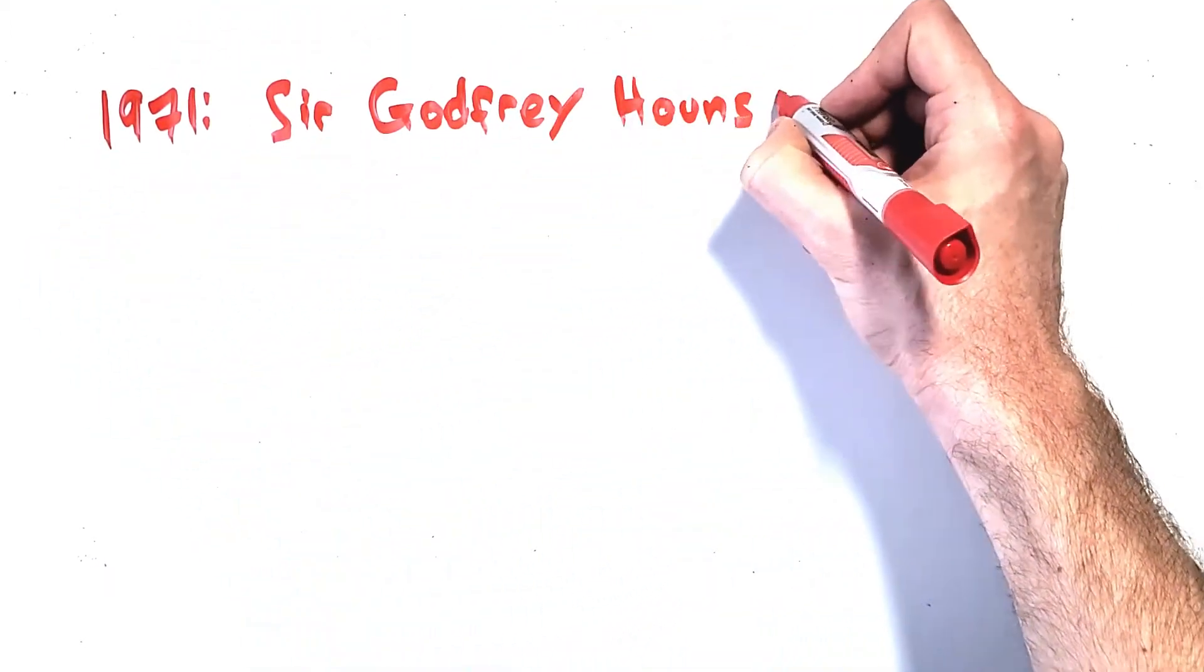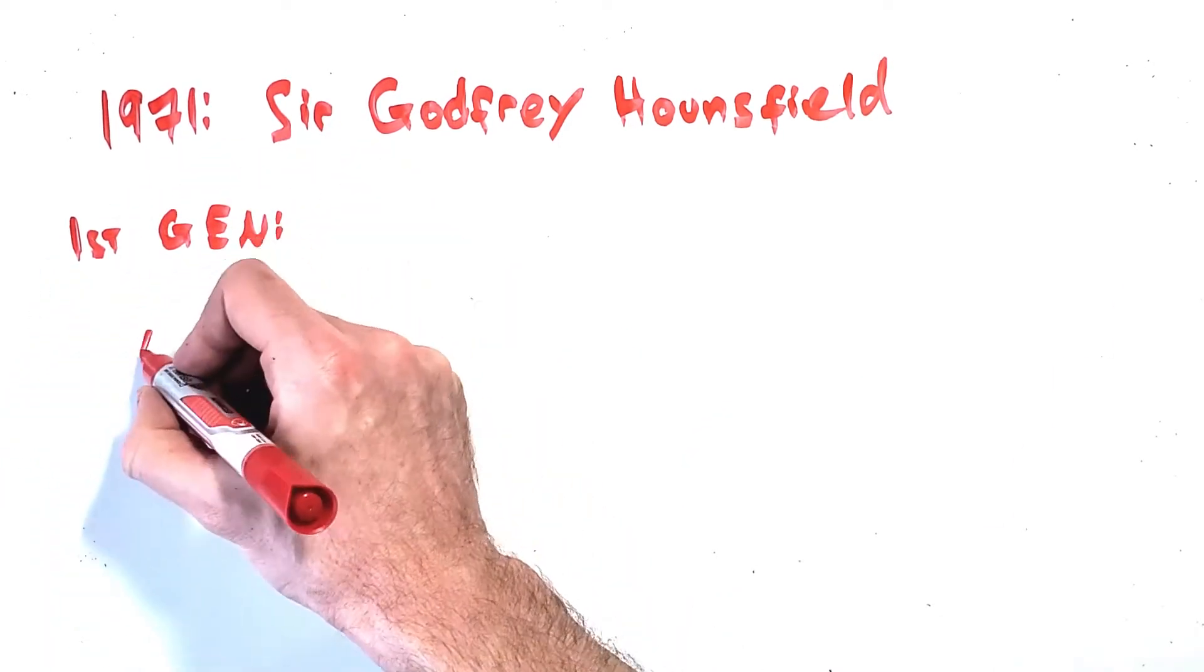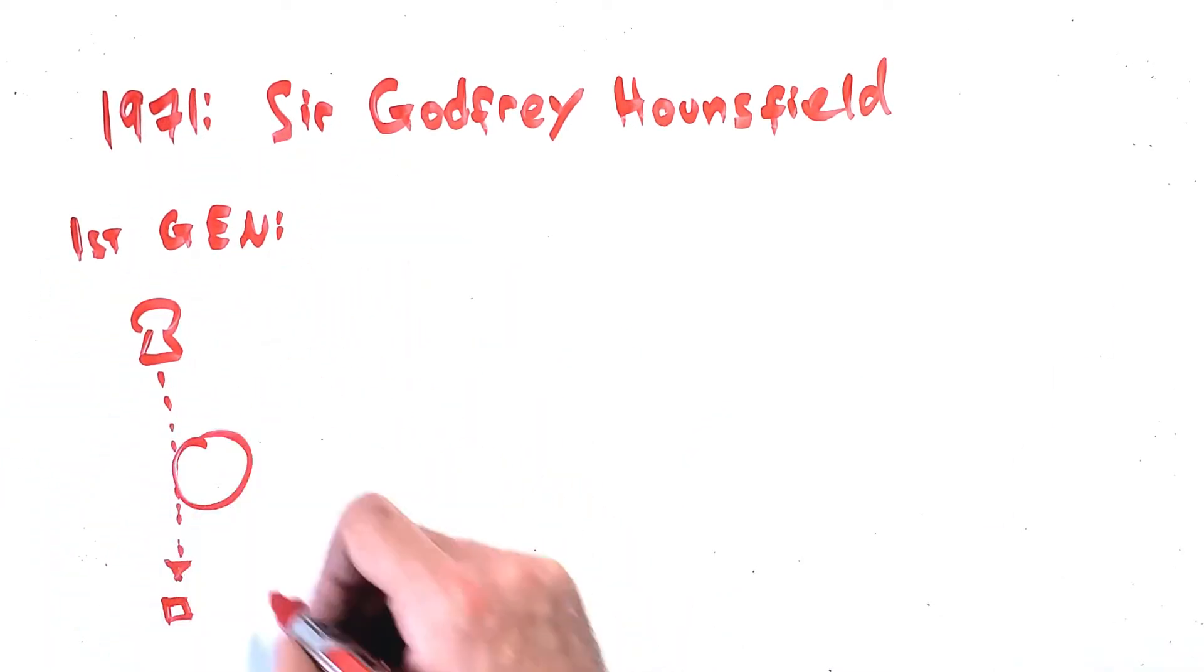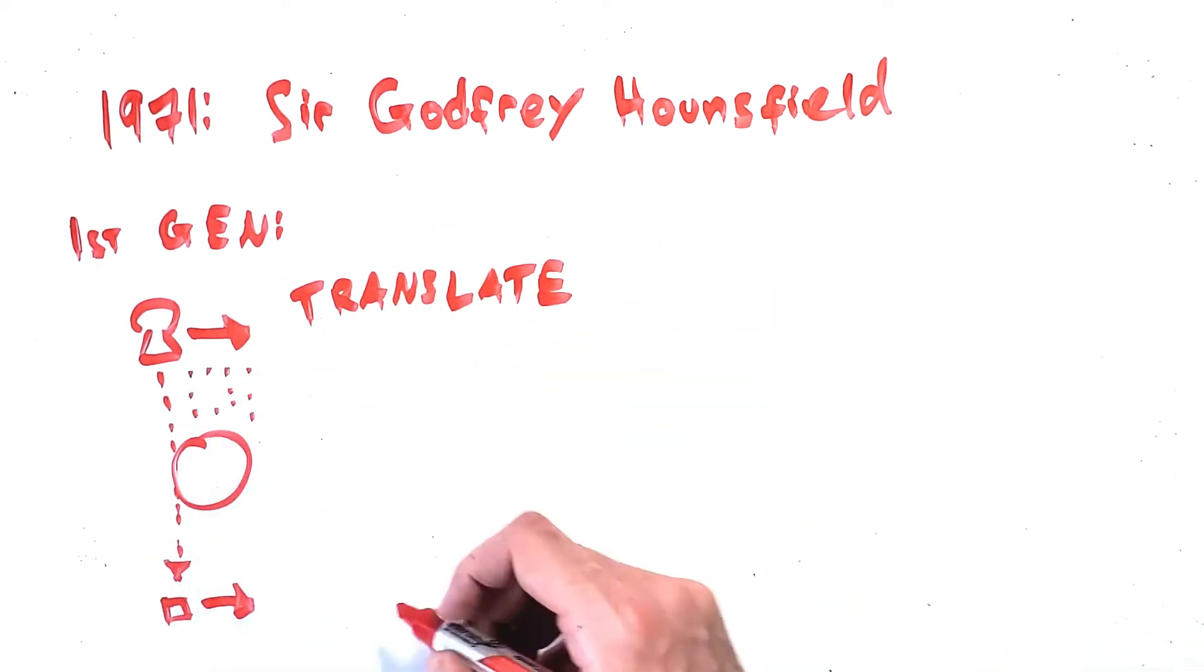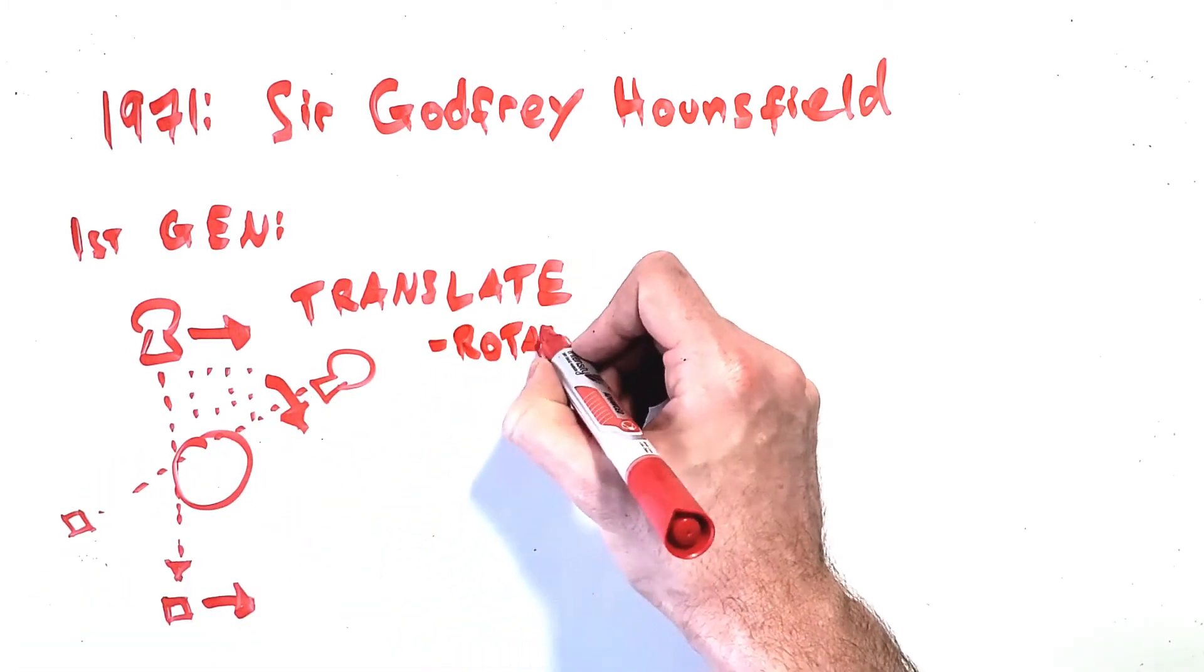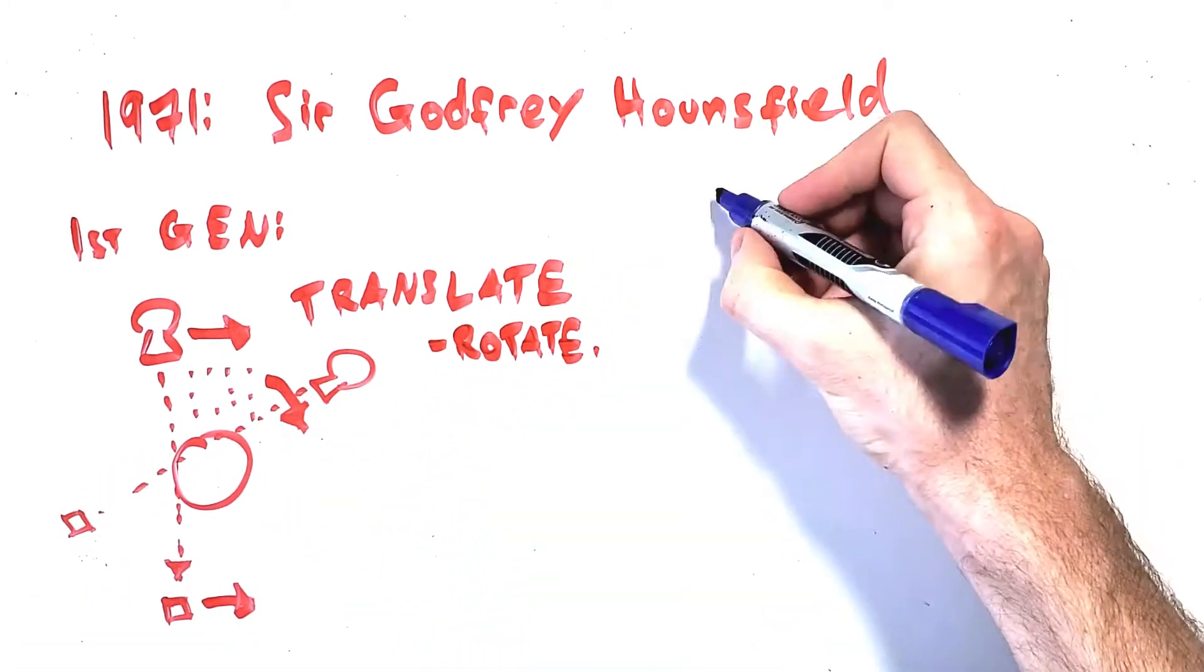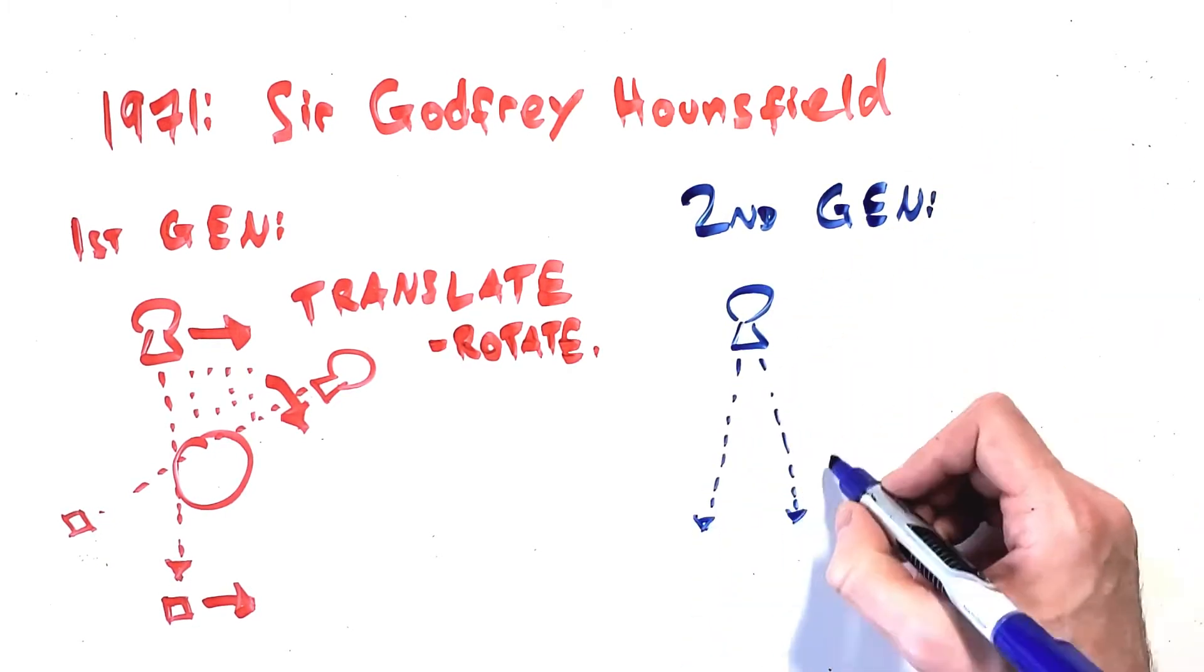The first CT scan was performed by Sir Godfrey Hounsfield in 1971, and the first generation of scanners used a translate-rotate motion where a single detector element would be exposed sequentially by a pencil beam while translating widthways across the patient. Then the whole system would rotate one degree at a time and repeat the process. Needless to say this took a very long time.